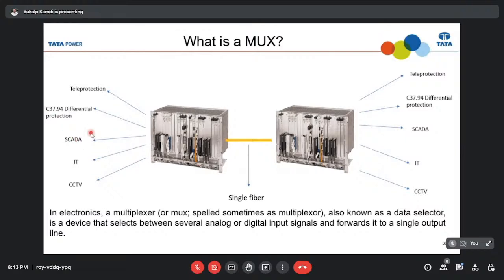If you recall, I mentioned that in differential protection, whenever you have abundant fiber, you can simply connect two relays through direct fiber. But if I'm not having direct fiber, I'll use the C37.94 protocol for the relay, connecting it to my multiplexer at one end and getting it out at the other end through the multiplexer. The relay will communicate simply through this communication media.